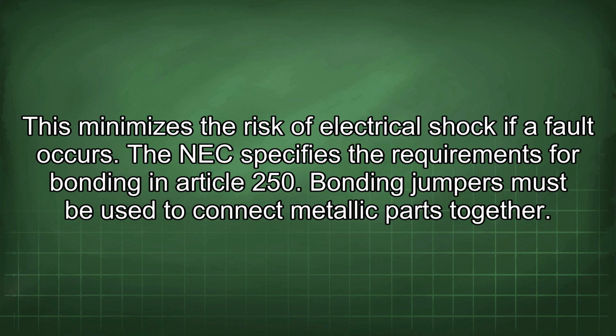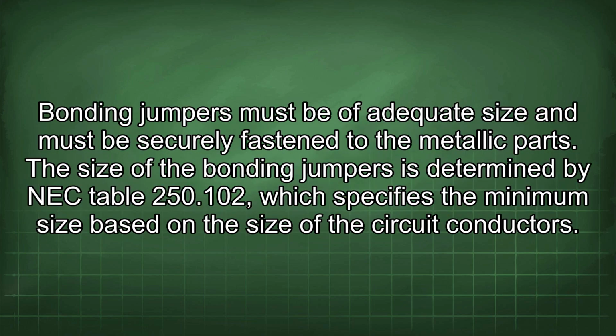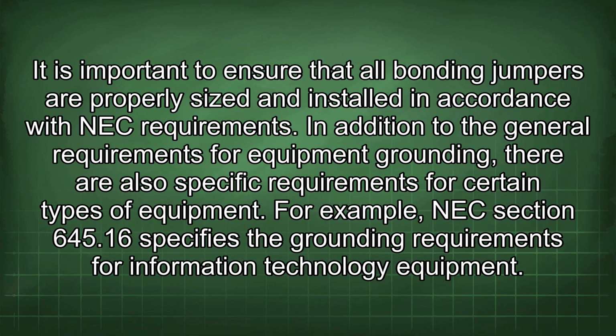Bonding jumpers must be used to connect metallic parts together. Bonding jumpers must be of adequate size and must be securely fastened to the metallic parts. The size of the bonding jumpers is determined by NEC Table 250.102, which specifies the minimum size based on the size of the circuit conductors. It is important to ensure that all bonding jumpers are properly sized and installed in accordance with NEC requirements.